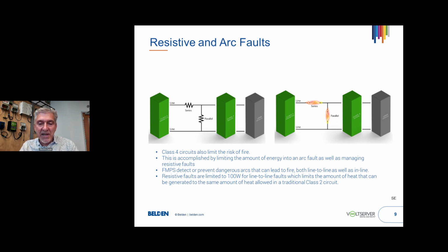It'll go to a high resistance state or high enough that if you plug a toaster oven into that outlet, it will heat up enough to melt down the outlet devices. And it's a very common cause of fire, electrical fires. That particular fault, again, has not ever been detected by conventional technologies. It's very difficult to detect because it's not a touch fault or a ground fault. It doesn't arc at all. And to the circuit breaker, it's not actually drawing more power than the circuit is rated for. So that is why it's such a problematic fault and such a cause of problems in the field, a very dangerous fault. So one class of fault managed power systems will detect resistive faults.